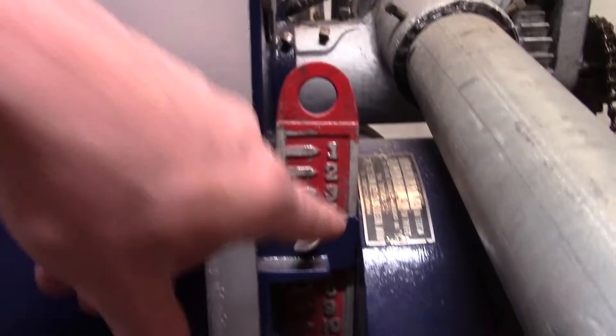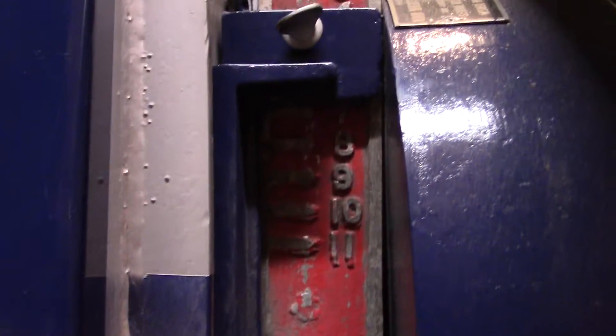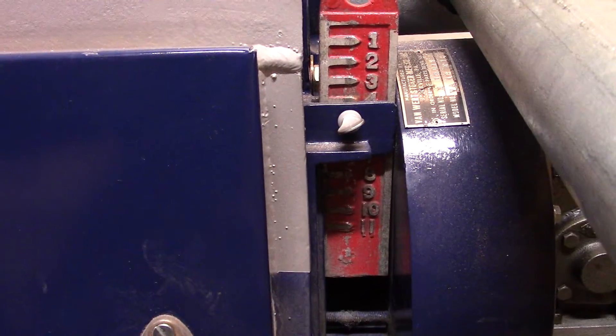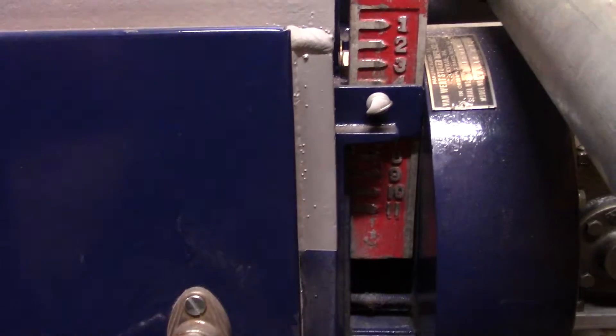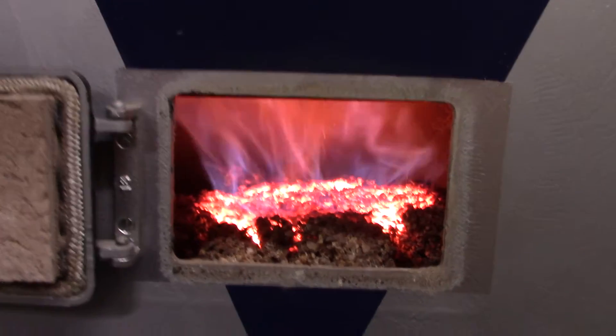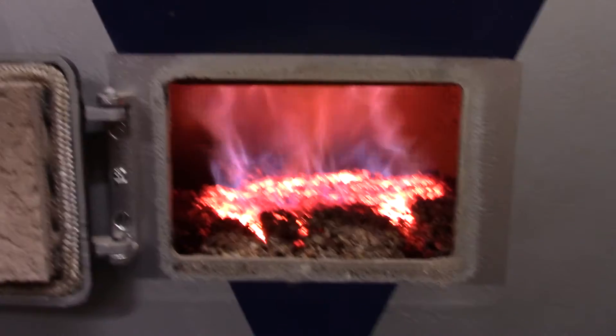It's pretty interesting that most only go to 3, because the air gauge actually goes to a higher level. It's a different thing that fits in that slot there — it covers up the inlet of the blower, and the higher numbers mean the air inlet is less blocked. We're going to run it like this for a while and see what happens; at the very least, we're going to have to be increasing the air a bit.